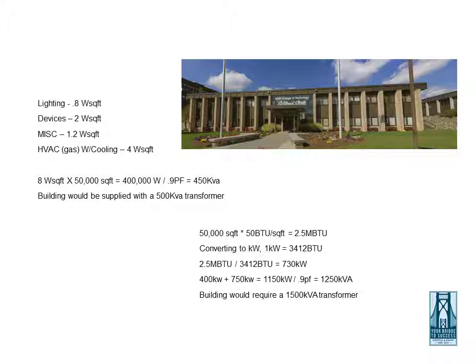Real estate considerations. As our need for additional power become necessary, there will be an increase in the size of equipment. To get a general understanding, we're going to use a 50,000 square foot building with average loads and some rules of thumb. In complying with the 2020 Energy Conservation Code, LED lighting would be around 0.8 watts per square foot. Devices, an additional 2 watts per square foot. Miscellaneous loads of 1.2 watts per square foot. And typical HVAC for gas-fired heating equipment and cooling adds 4 watts per square foot.